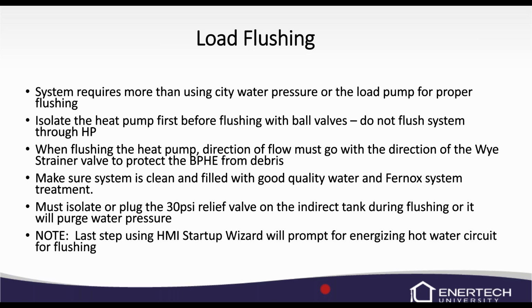Again, isolate or plug the relief. Now don't leave the relief plugged, but if you need to plug it while you're flushing, that's okay. Just remember to remove it, or else it will purge water. If it's going to a drain, not a big deal. It's going to purge a little bit of water, not a big deal. It could suck a little bit of air in when you do that though, so just be careful.